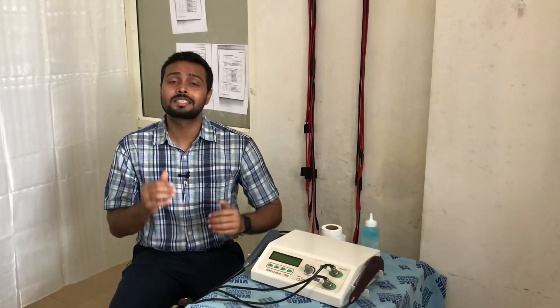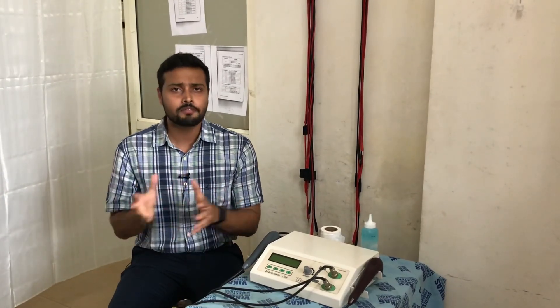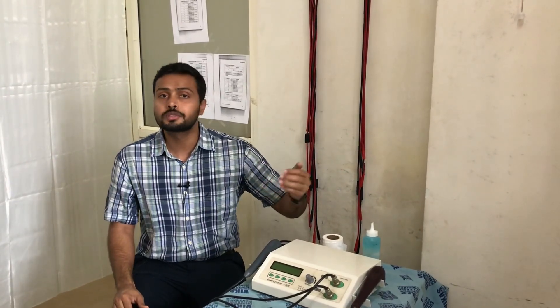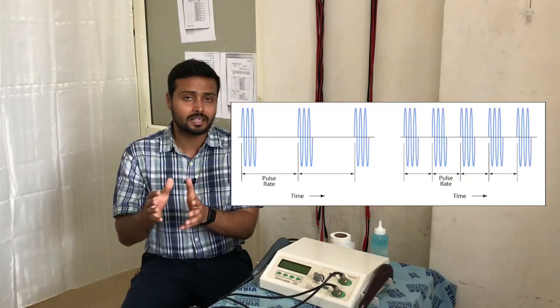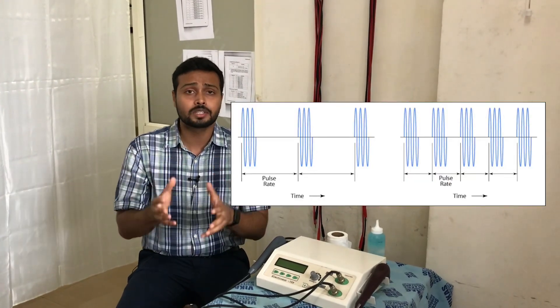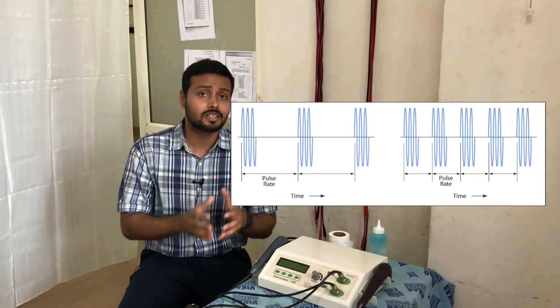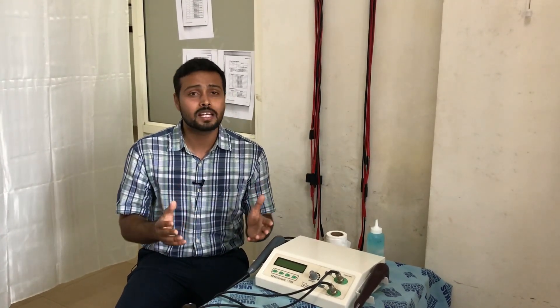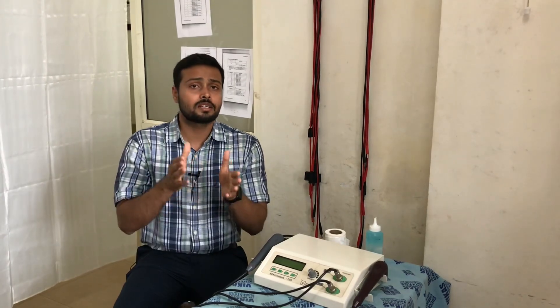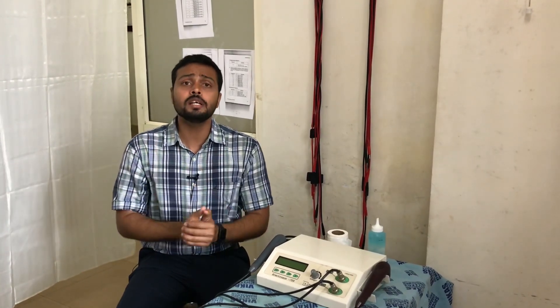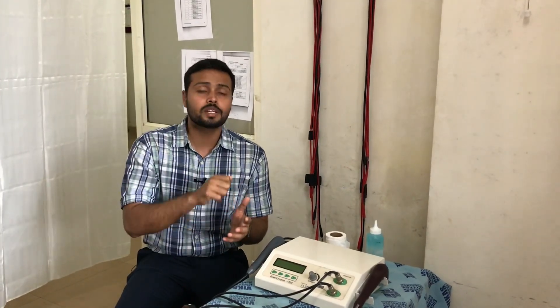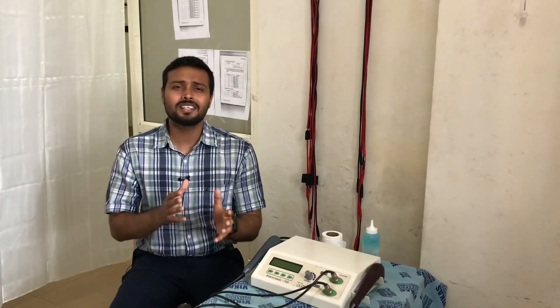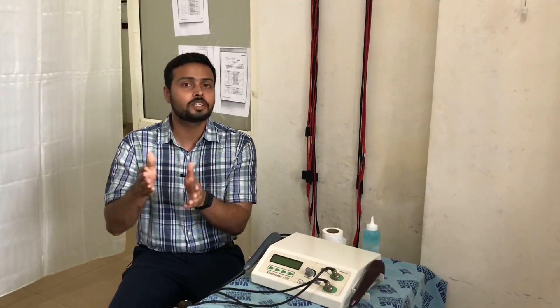There is also continuous ultrasound and pulsed ultrasound. Continuous means the waveforms are continuously given. Pulsed means there is a duty cycle — normally 20% is used, meaning ultrasonic waves are given 20% of the time and the remaining 80% is rest. For example, in a 10-second period with 20% duty cycle, waves are given for 2 seconds and there is an 8-second rest. The formula to calculate duty cycle is: on-time divided by on-time plus off-time.